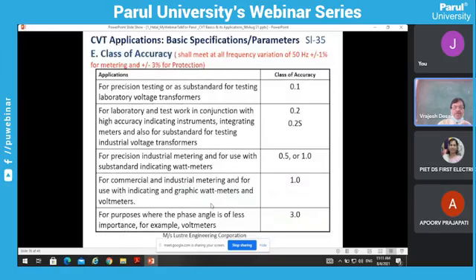Now coming to the class of accuracy. Class of accuracy is very important for metering purpose because this voltage point is always connected to the energy meter. So correct output from the line voltage has to be there. There is 0.1 class, 0.2 class is also there, then there is 0.2S class, which is a more accurate class. Then for commercial industry metering we can have a slightly lower class, that is class 1. Then you can have class 3 also for normal monitoring of the voltage.